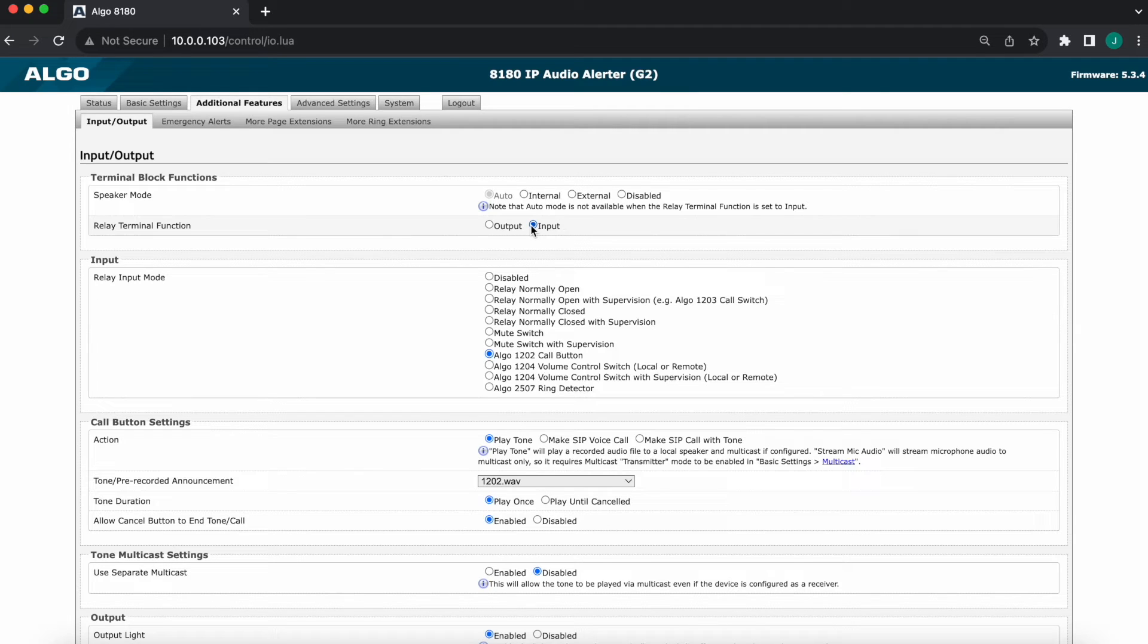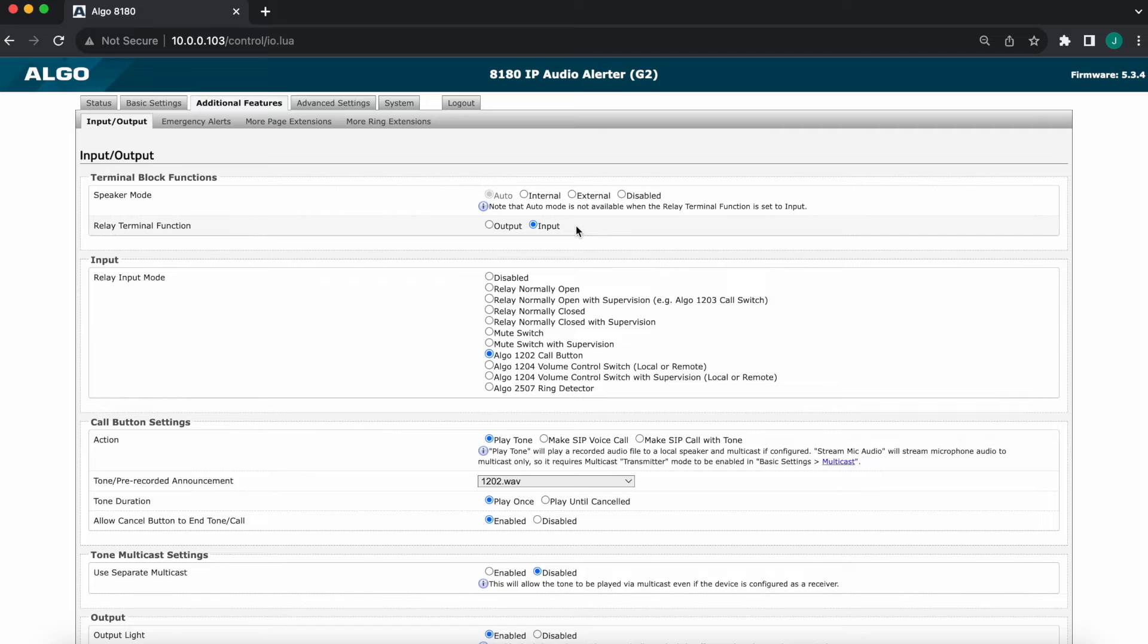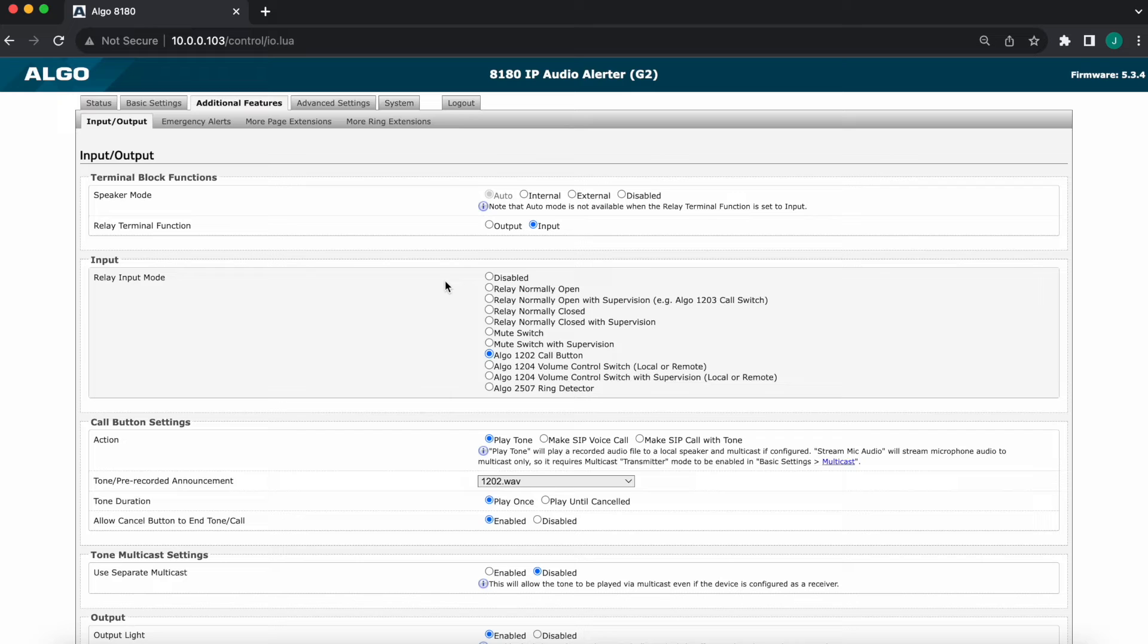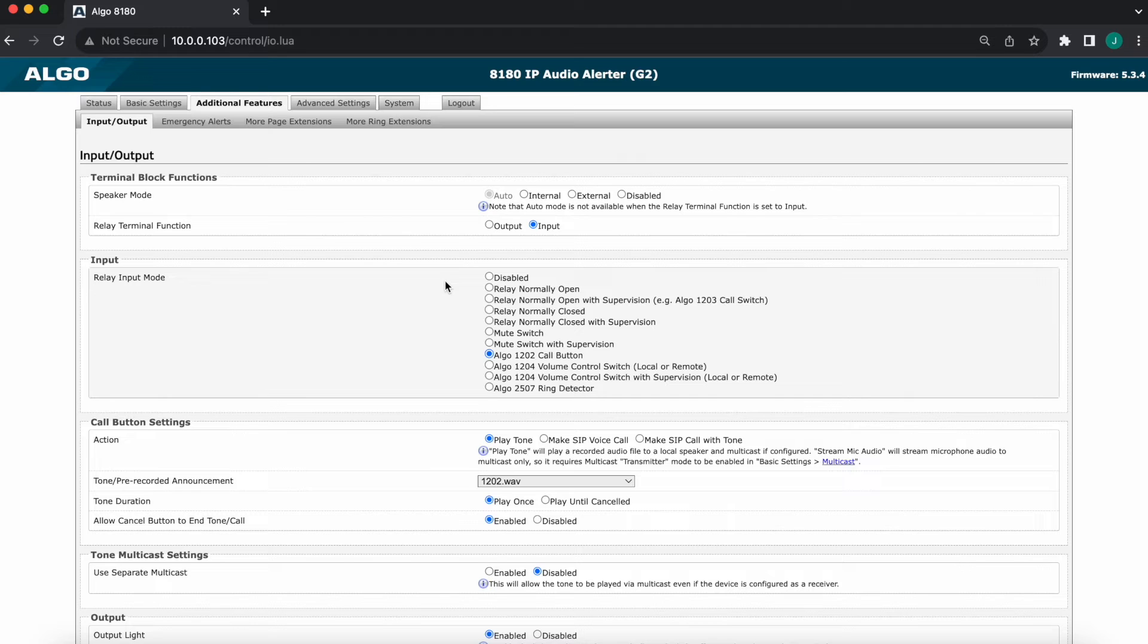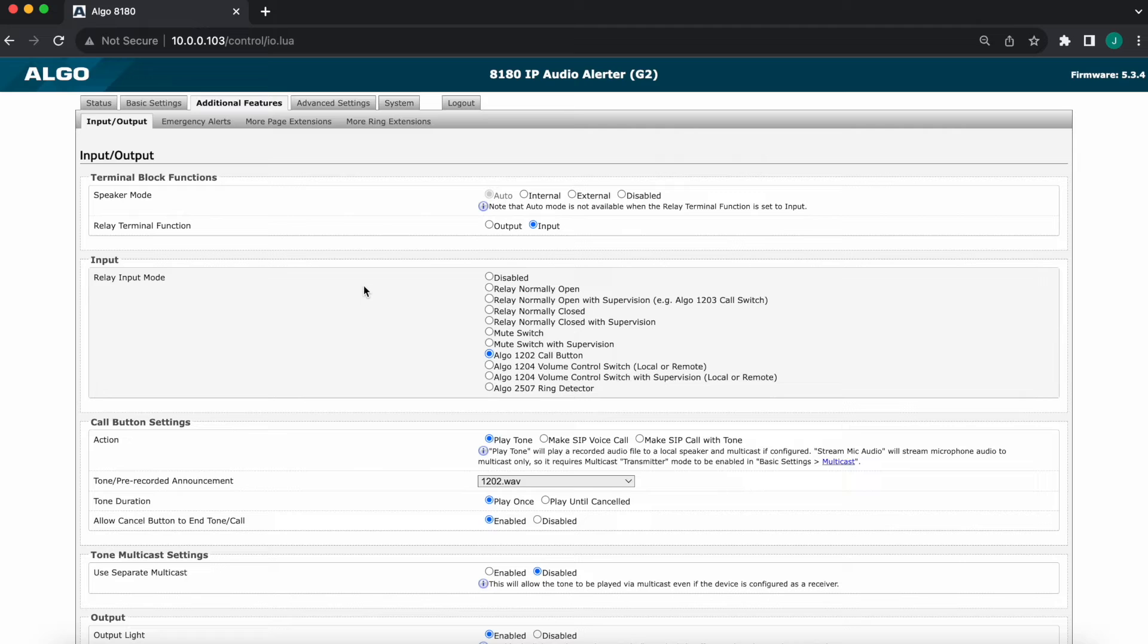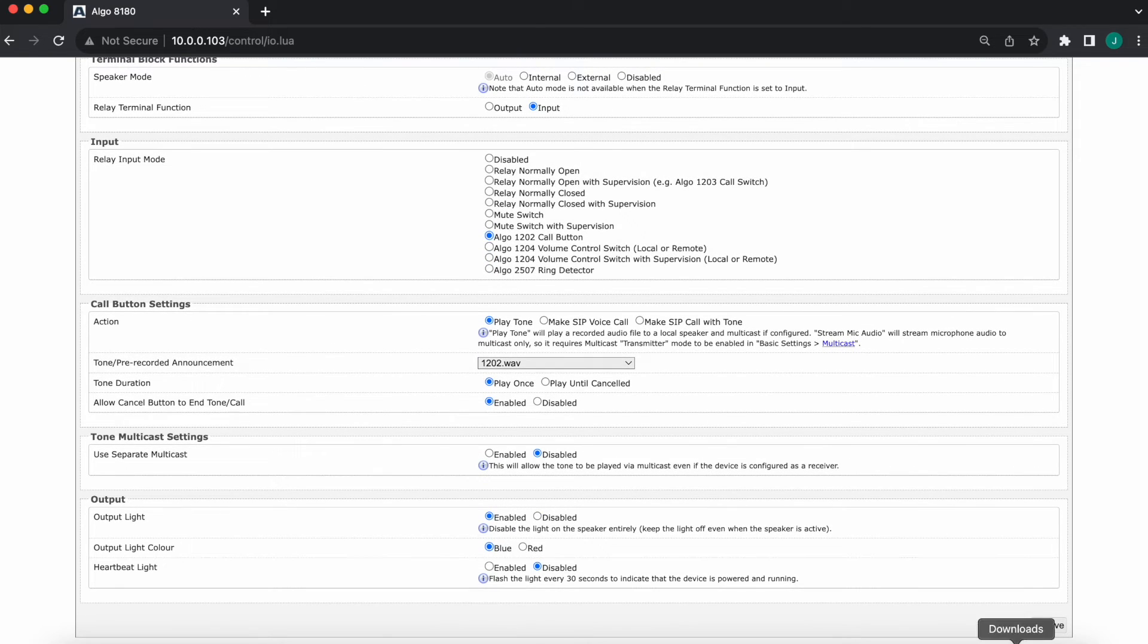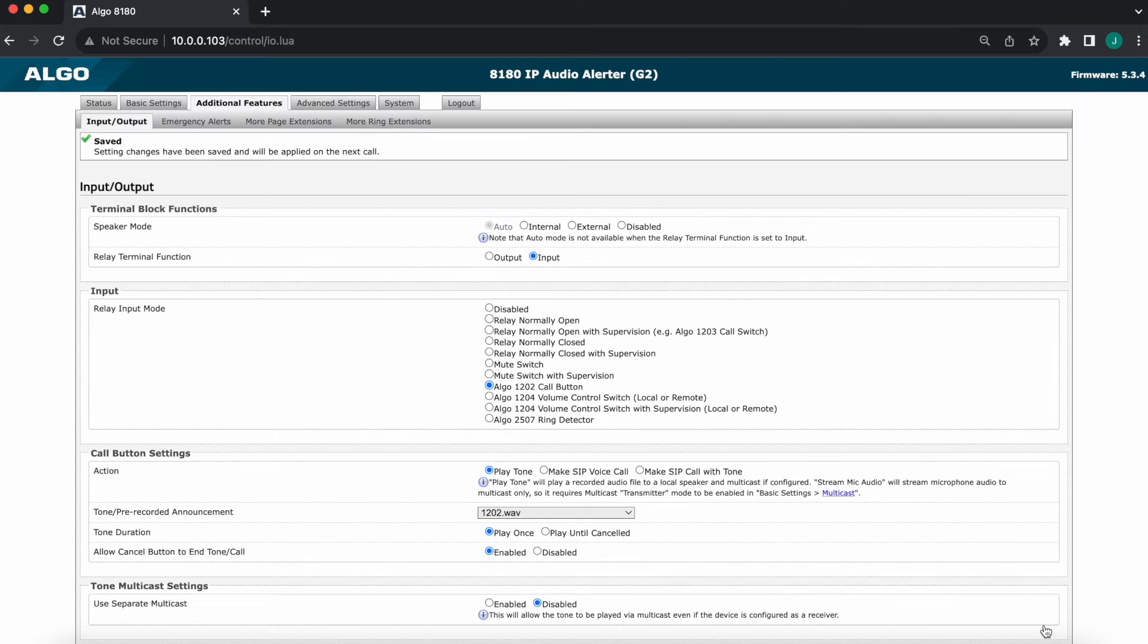You would not get an option for output or input on 8128, on 8186, 8188, and so on and so forth, because they have separate terminals for input and output. But once we select input, we're able to select to configure the relay input mode. Again, the 8180 is connected to the 1202, so we'll set it up to 1202 call button mode. As you can see here, there's different options for different accessories that we offer or simply for a standard normally open relay, normally closed relay, if you were connecting any kind of third-party device that is just looking for a dry contact closure. Again, we want 1202 mode, so I'll go ahead and save it for now. We'll come back to the actions in a second, but as soon as I save it, you see that the light illuminates. So it is turned on now.